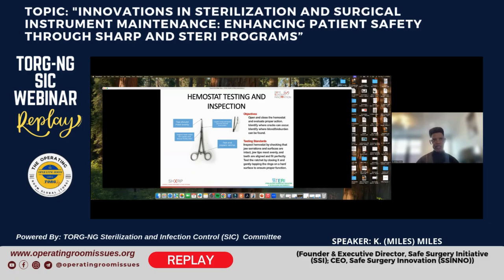Next, you want to test the ratchet. That's going to be down at the bottom with the rings. And then you want to make sure that it's engaging properly into that first and second ratchet. That's going to make sure that when the surgeon closes that instrument, it's going to stay closed and it's not going to spring out while you're in the process of doing surgery.